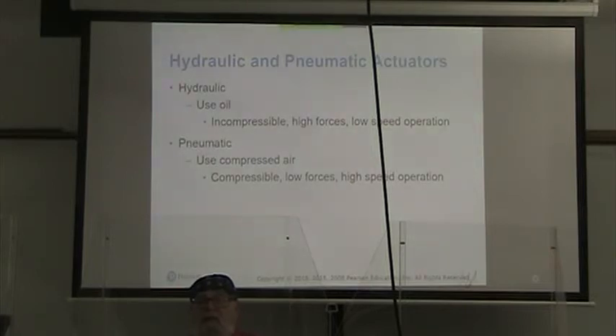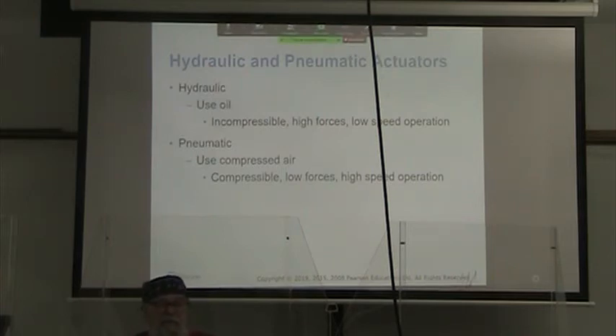Hydraulic and pneumatic actuators. Hydraulic actuators usually use oil even though hydraulic comes from hydro for water. We consider that oil to be incompressible. It's capable of very high forces, but we consider this to be a low speed operation. When we talk pneumatic, we're using the same principle, but in that case we're using compressed air. The air can be compressed further. Usually this is used for low forces, but high speed operation.